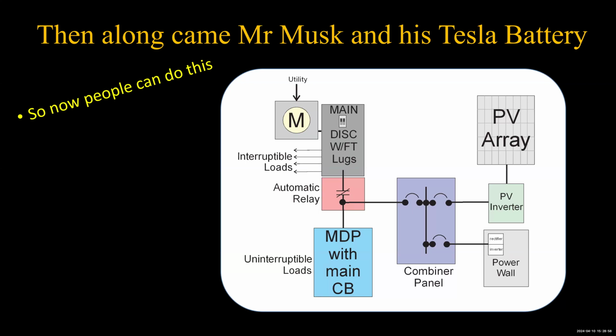So you've got some losses on the AC to DC conversion for charging the battery, and some more losses when you discharge from DC to AC. But those losses are relatively small, in the 3 to 5% range each direction. So your round trip efficiency on this thing can still be somewhere pretty close to 90%, and sometimes higher.